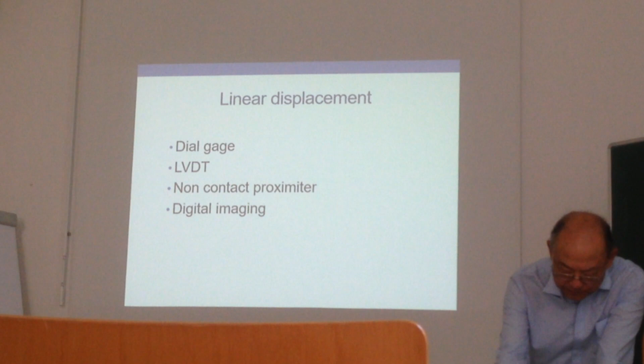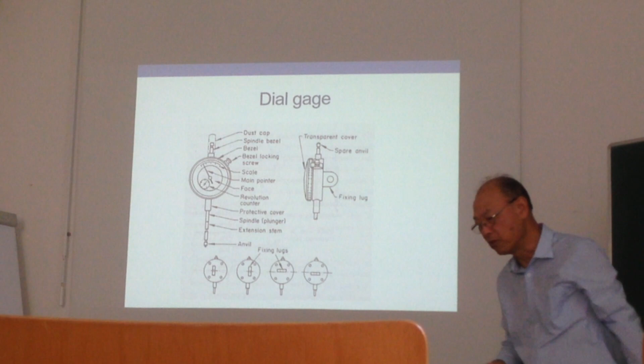But basically we'll look at the first two. The dial gauge is basically just a rod, which we call a spindle, and inside the gauge is a series of gears — a large gear and a small gear. A little bit of movement in the large gear will cause a lot of movement in the small gear, and that gives you the sensitivity.